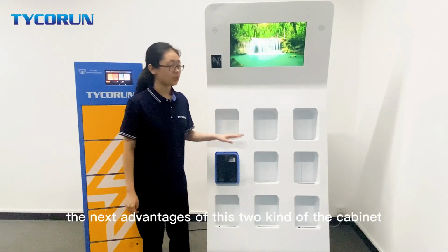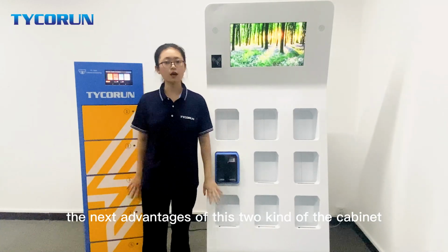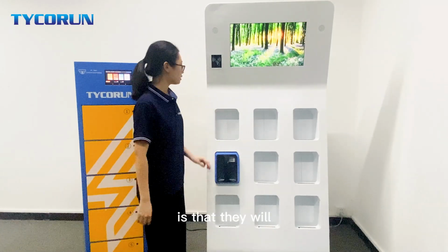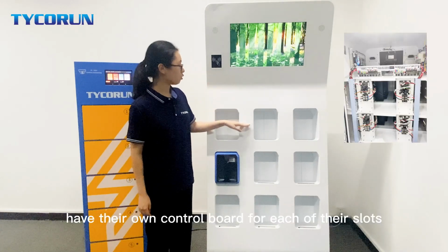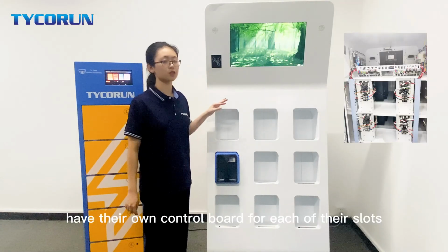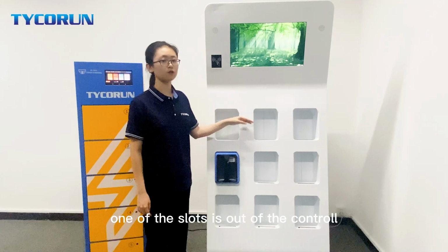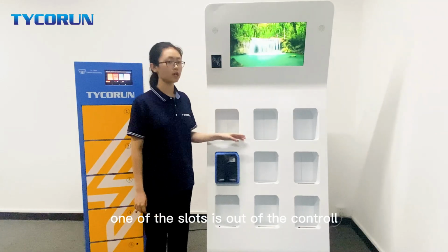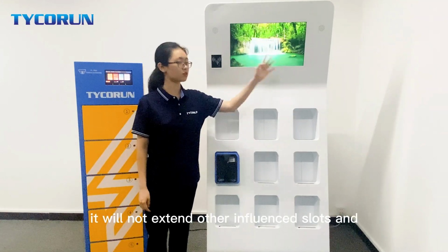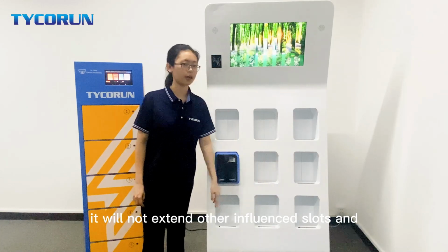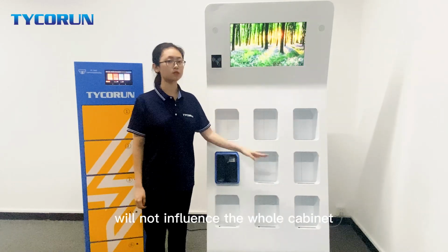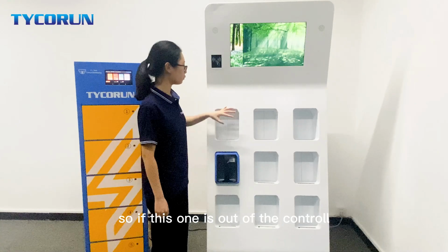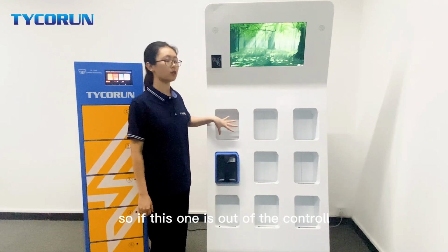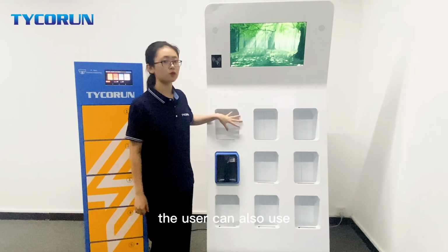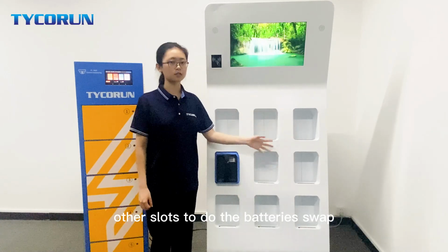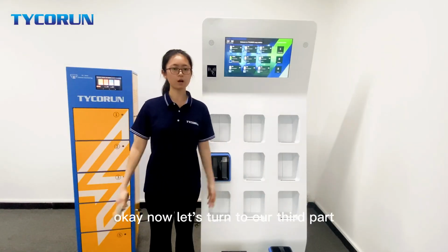And the next advantage of these two kinds of cabinet is that they have their own control board for each of their slots, which means that if one of the slots is out of control, it will not affect other slots and will not influence the whole cabinet. So if this one is out of control, the user can also use other slots to do the battery swap. Okay, now let's turn to our third part.